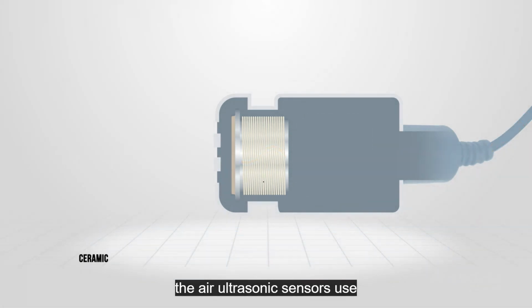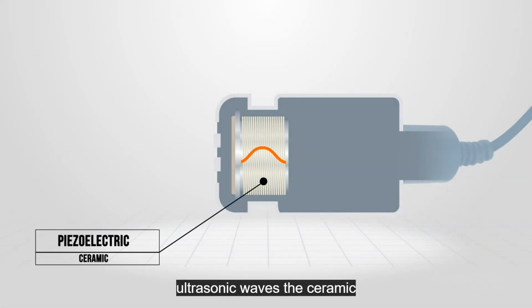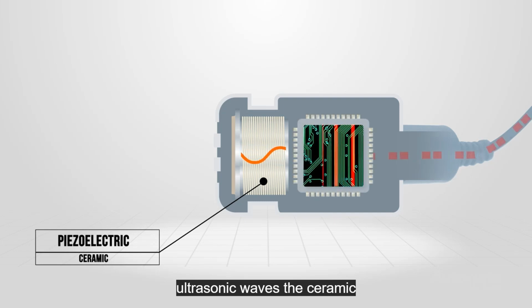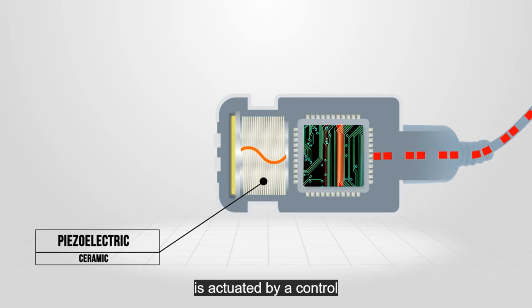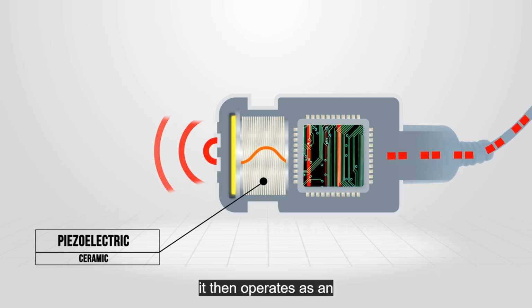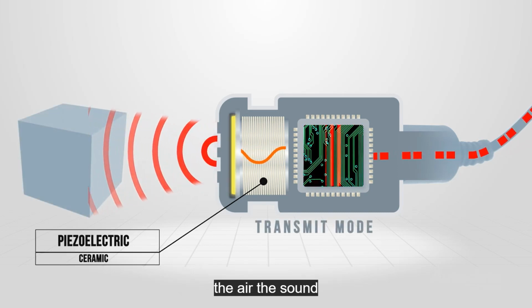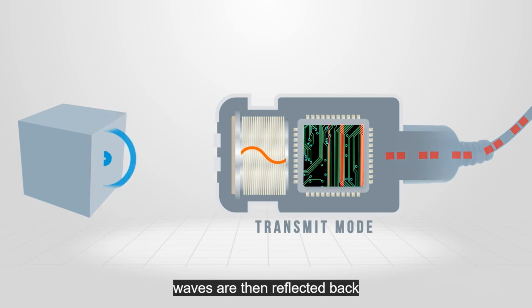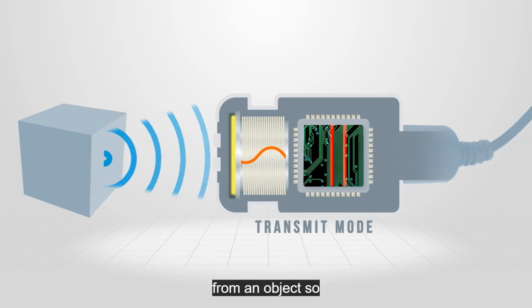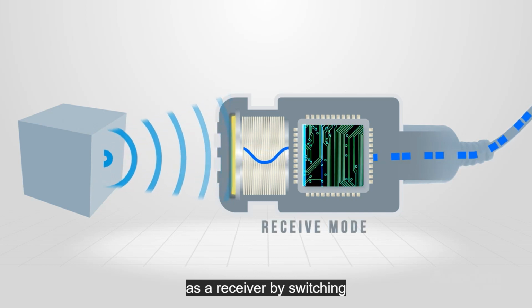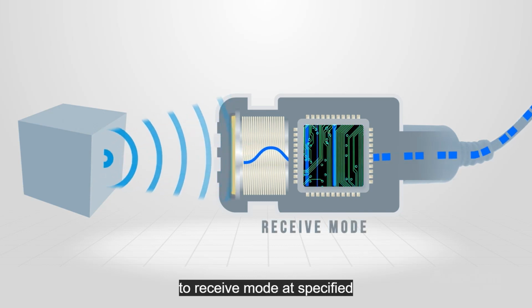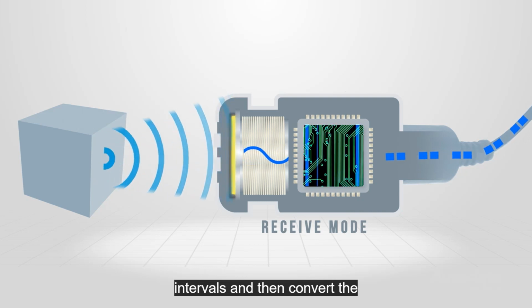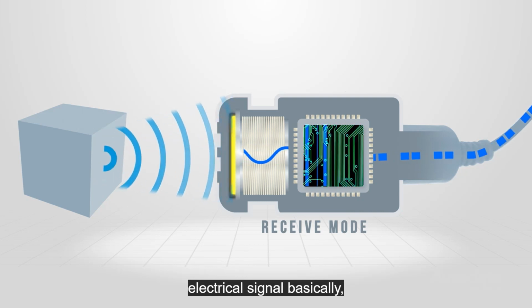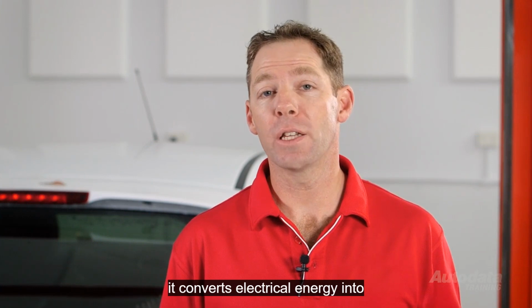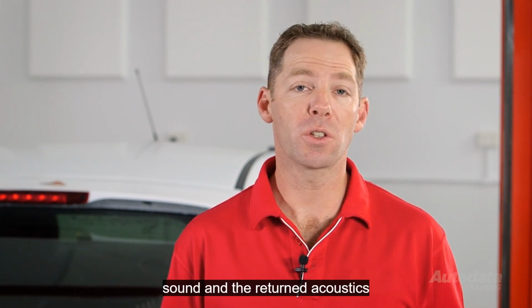Ultrasonic sensors use a piezoelectric ceramic to produce ultrasonic waves. The ceramic is connected via electrodes and is actuated by a control from the module. It then operates as an emitter for sound waves into the air. The sound waves are then reflected back from an object, so the transducer will also serve as a receiver by switching to receive mode at specified intervals, and then convert the sound waves back to an electrical signal. Basically, it converts electrical energy into sound, and the returned acoustics back into electrical energy.